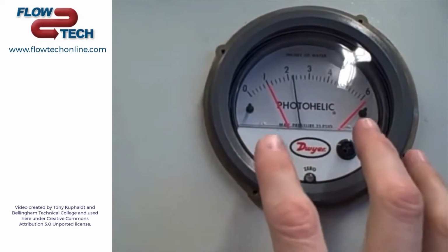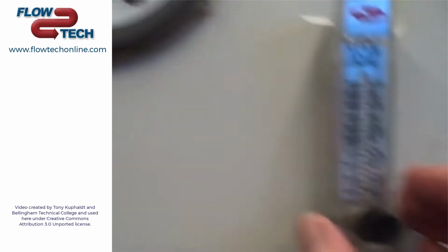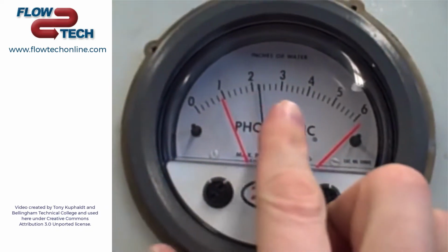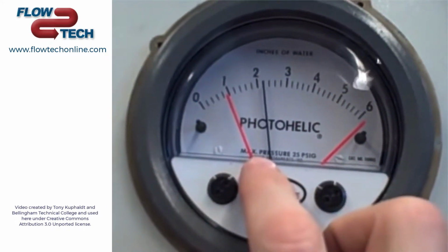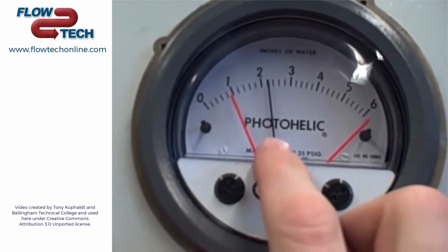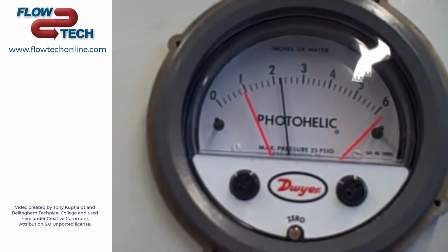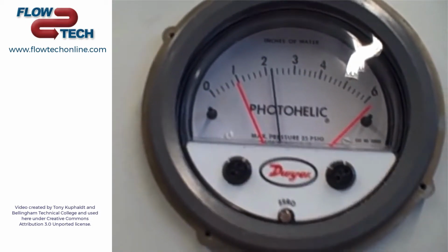But part of this system, an essential part of any bubble tube system, is some sort of flow indicator to let you know when you do have purge gas flowing into the bubble tube. So here, the rotameter serves that purpose. And you can see here, if you look closely at the Photohelic gauge, you can see the needle bounce back and forth. That's because of the individual bubbles exiting the end of the bubble tube. So I could look at the bouncing rate of that as a crude indication of flow rate.